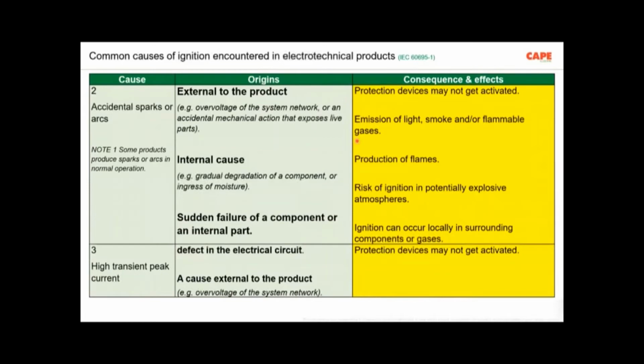But it is very unfortunate that this protective measure is not very well taken care of. If you really ask how much voltage can go into an electrical installation, a low voltage electrical installation, due to a fault on the high voltage side of the transformer, I would say sometimes it is 10 kV or 20 kV or 50, 60 kV. Such high voltages can come inside our electrical installation. But remember, the maximum allowed is 1200. So the design must ensure that more than 1200 volts is not allowed inside your electrical installation due to a fault on the high voltage side. This is the exact part of this one line.